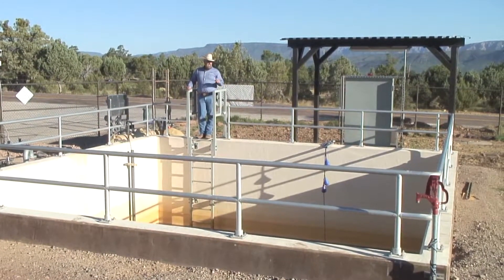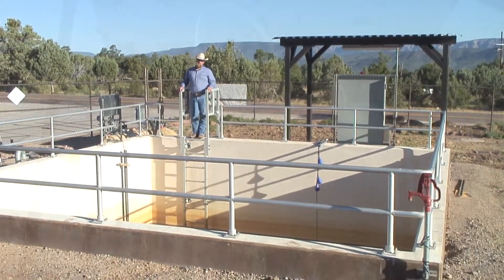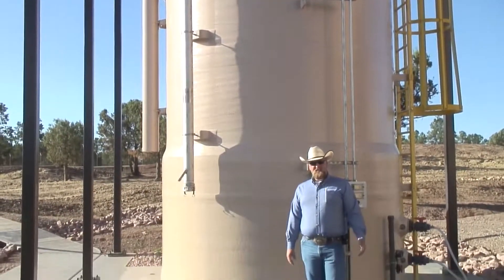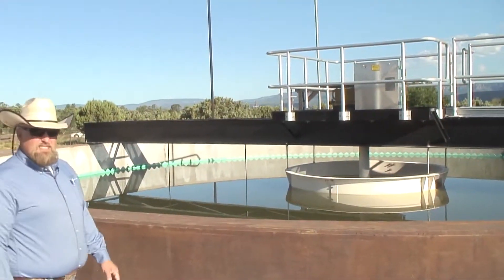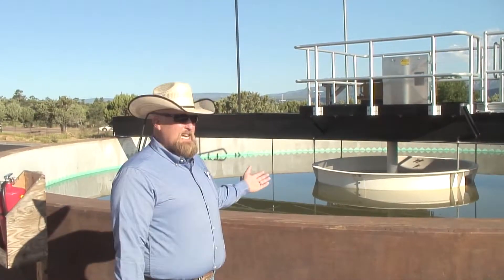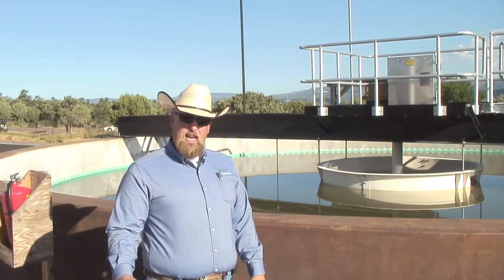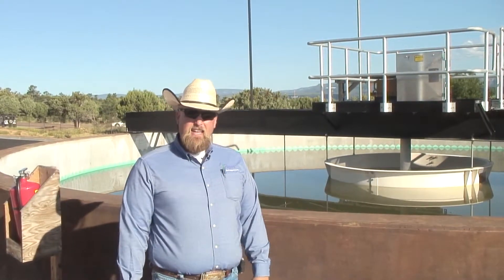This is the main lift station, where all waste from our treatment process goes. Water gets neutralized in this basin and either goes back to the clarifier — where we reuse 90 percent of the water — or it gets sent to the local golf course. This is our salt brine tank; another unique feature of this project is that we actually make our own sodium hypochlorite, or bleach, to disinfect the water. This is our recovery clarifier, where backwash water from the filters separates out clean water from sludge. The clean water is recycled back to the beginning of the treatment process, and the sludge goes to waste — recovering about 90 percent of our water overall.